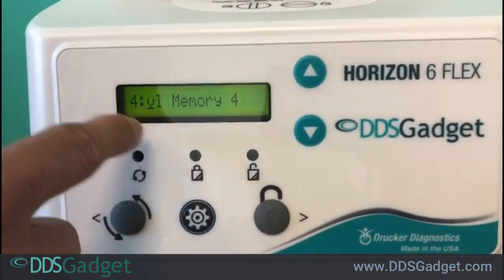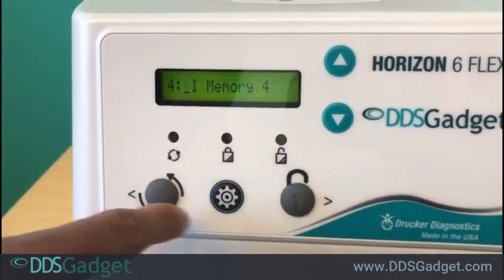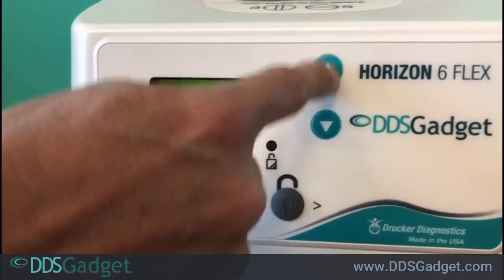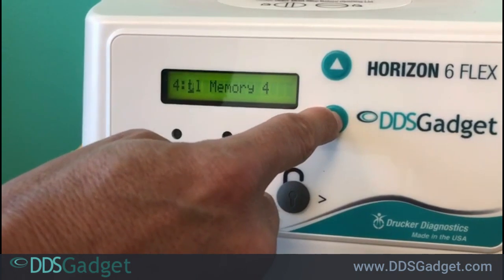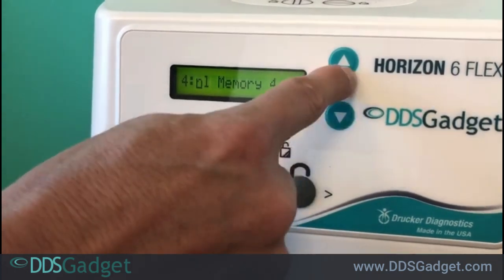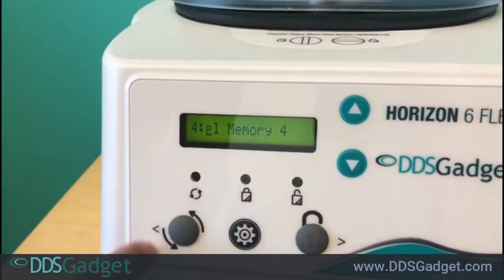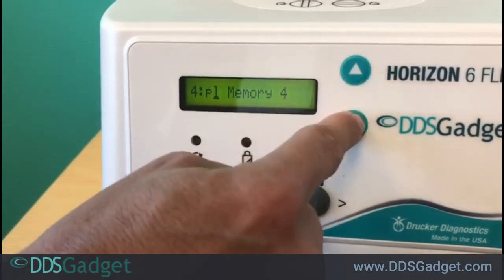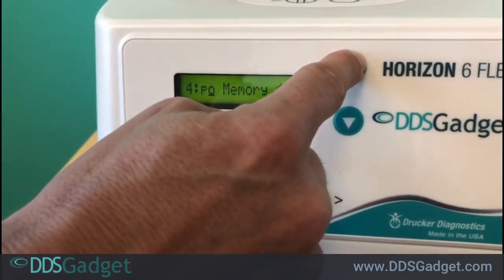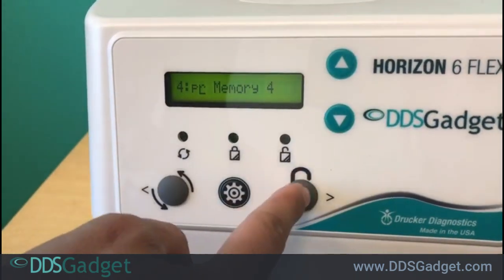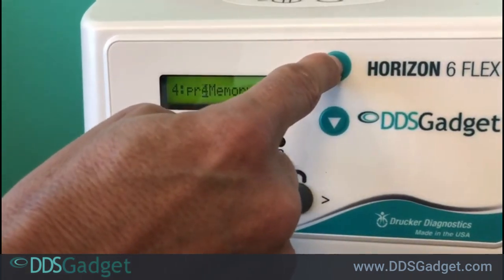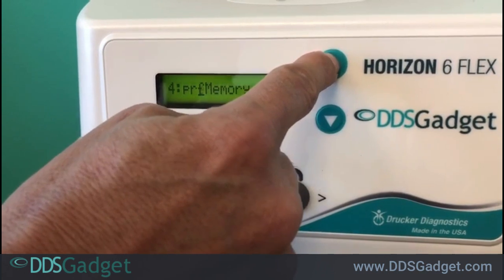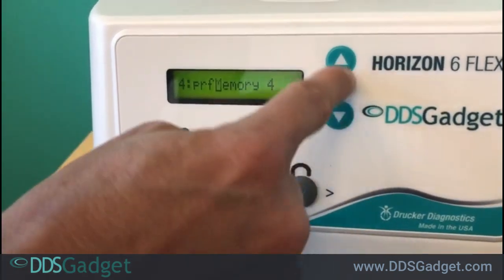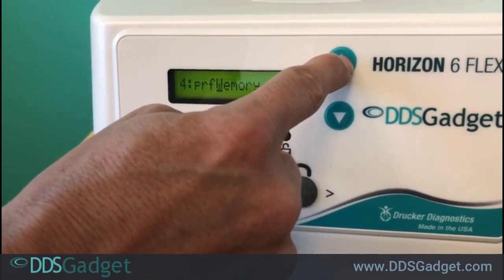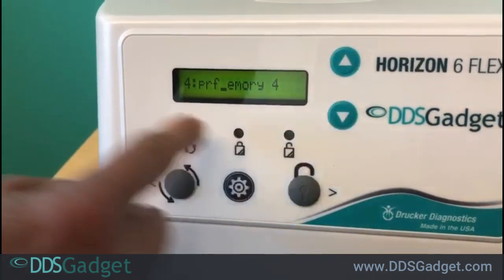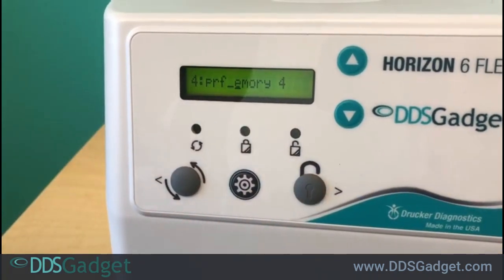Then the next setting is to actually name it, if you wanted to name it, and you name it by going to the up and down arrow to choose the letter. So let's say we wanted to just call this PRF. We would go to P. Once we chose the P, we then use the right arrow to get to the next letter, which we could then do R. Move to the next one. Move to F. Now, if you want to skip a space, you have to move towards the numbers. Once you get to 9, you'll see there's a space now. Now there's a space, then you can move to the next one.